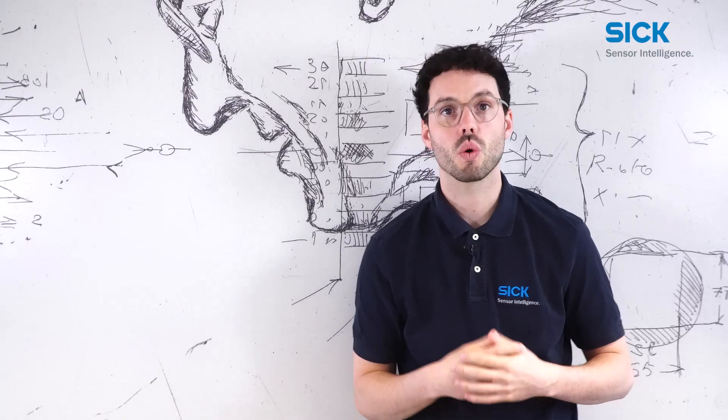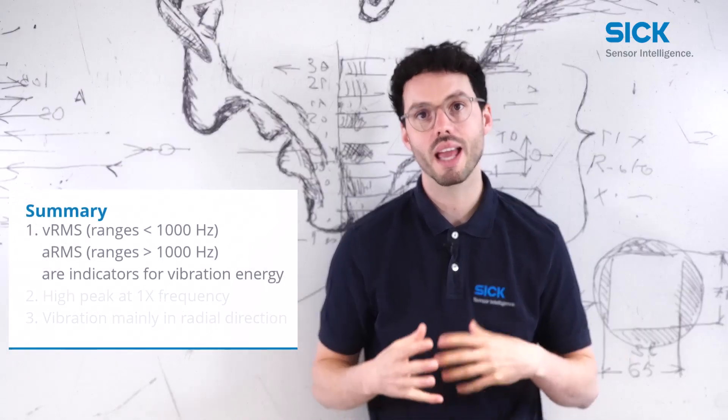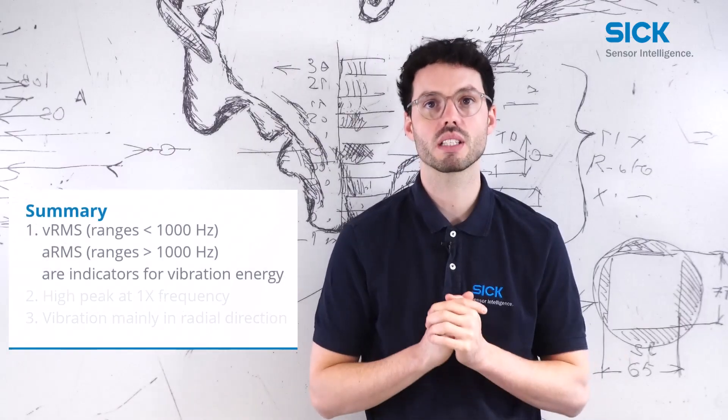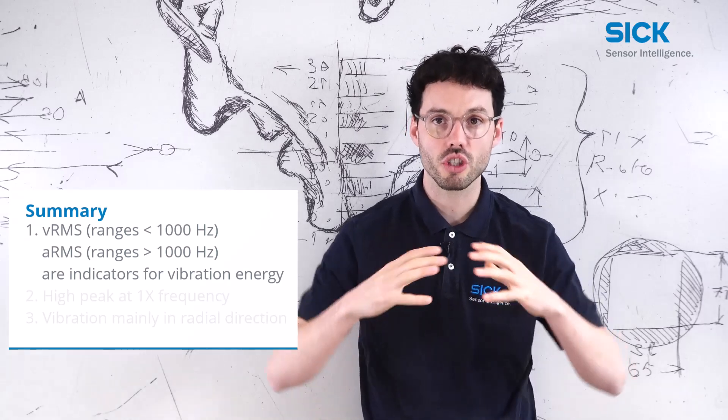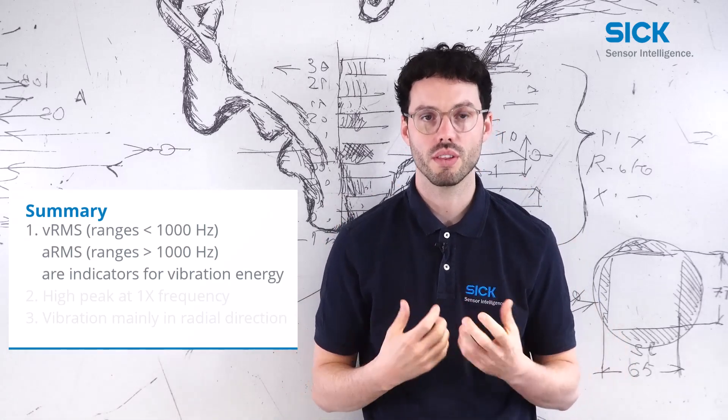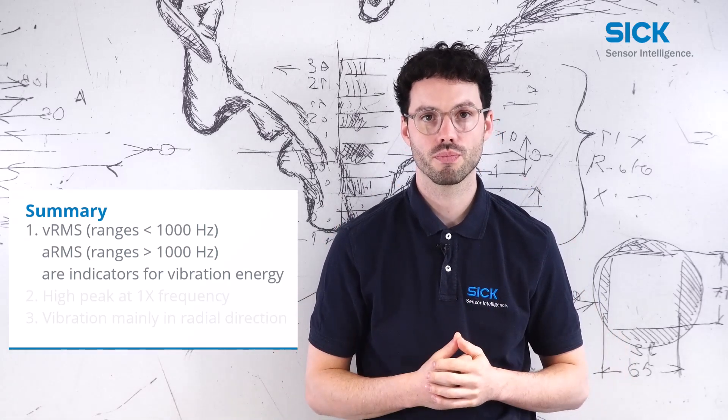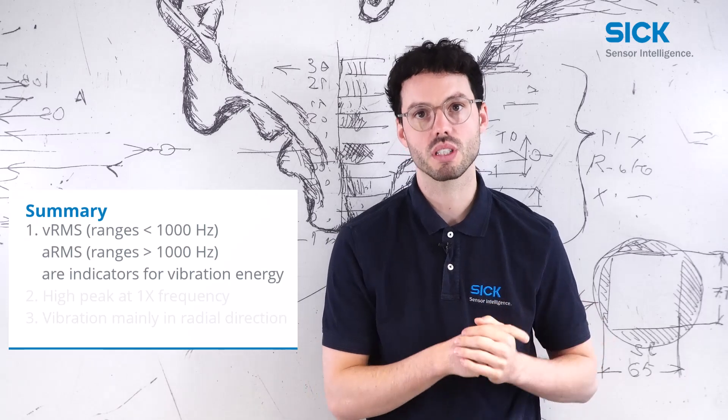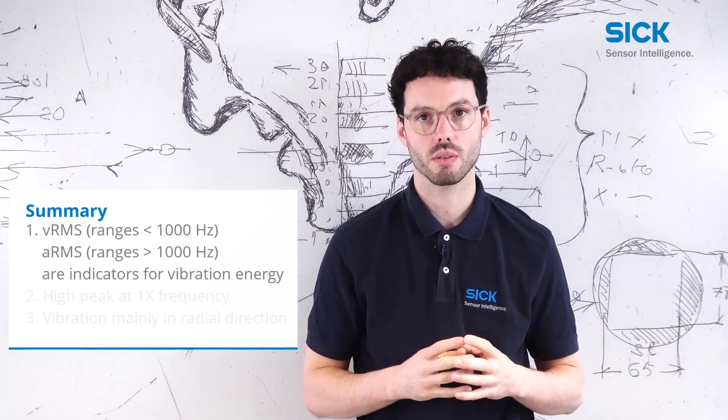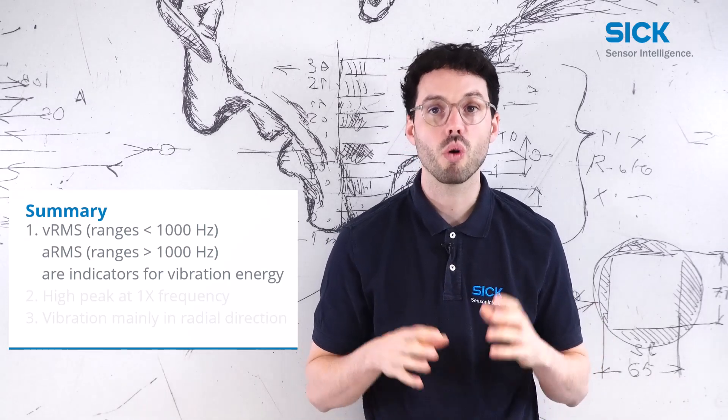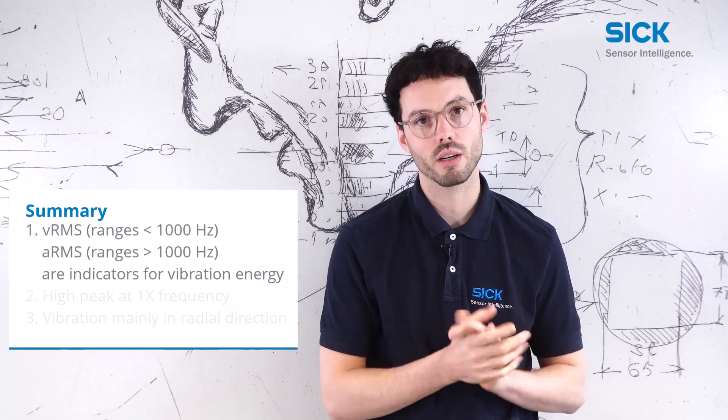So as a summary, the VRMS and the ARMS are good indicators to judge the overall energy within the vibration. Especially for low frequency ranges, the VRMS is relevant. For high frequency ranges, the ARMS.